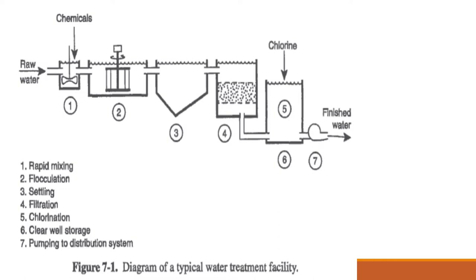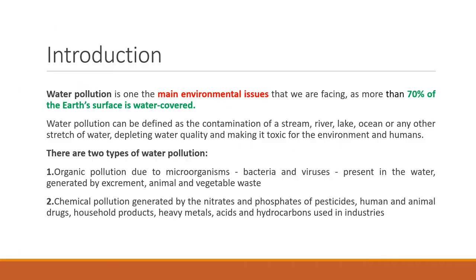The chemicals form bigger flocs which settle due to gravity. The top water is then sent to a filtration unit to remove finer particles. Finally, it is sent to a chlorination unit where it is disinfected, and then sent through the distribution system to houses. This is how a typical water treatment plant works.